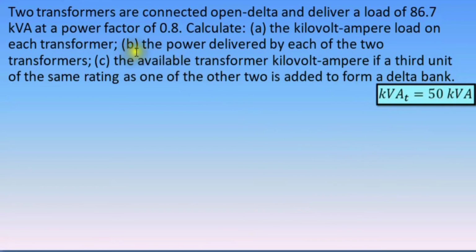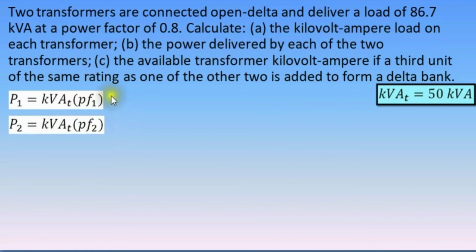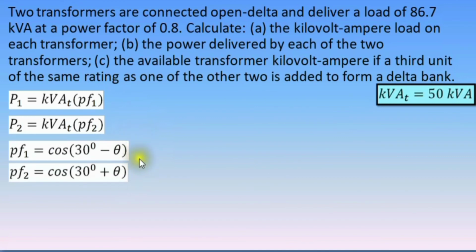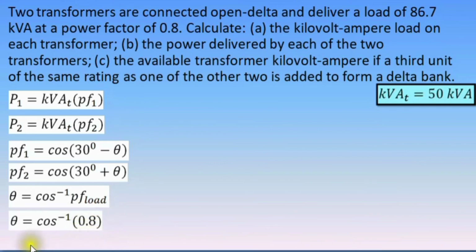Now for letter B, calculate the power delivered by each of the two transformers. Again, we use these equations. We already have the kVA of each transformer, that is 50 kVA. Let's compute the individual power factor of each transformer. To do that, we first need to determine the power factor angle of the load. So theta equals the inverse cosine of the power factor of the load. Substitute 0.8, that is the inverse cosine of 0.8, theta equals 36.87 degrees.